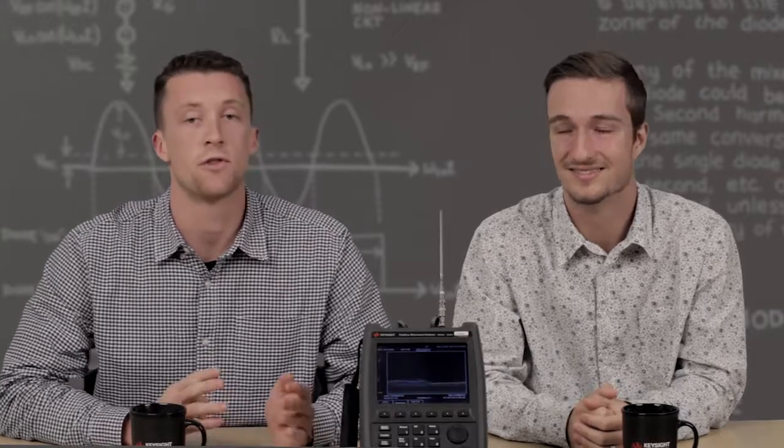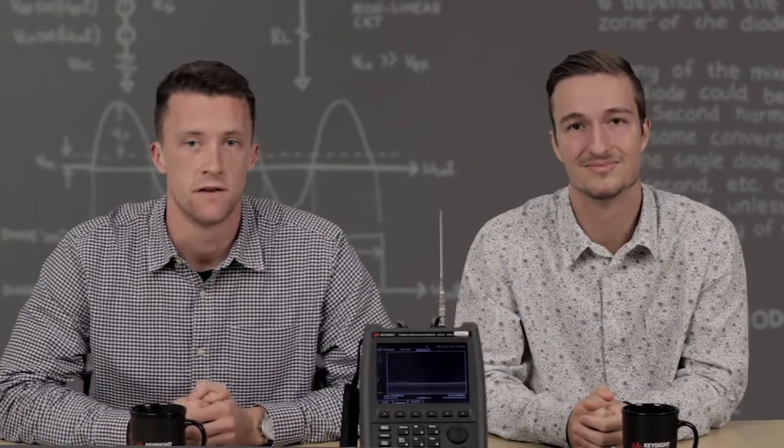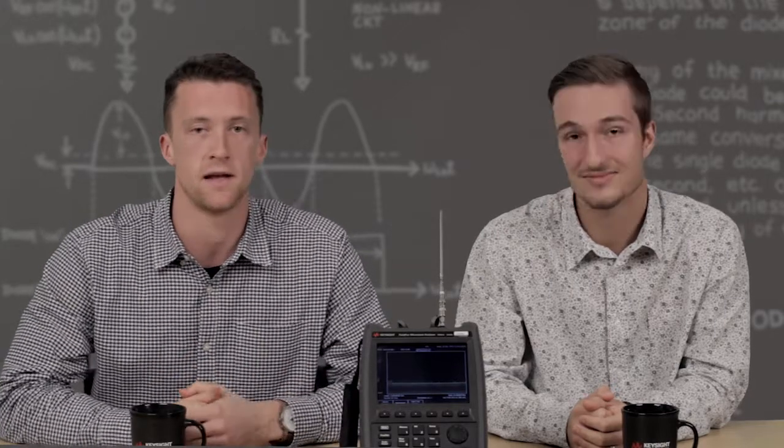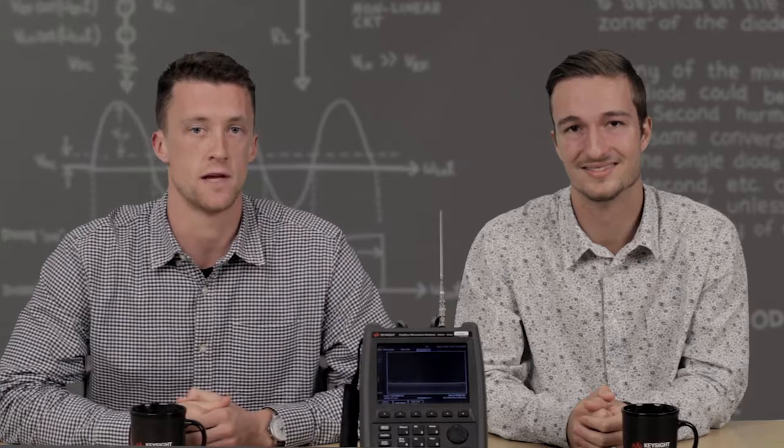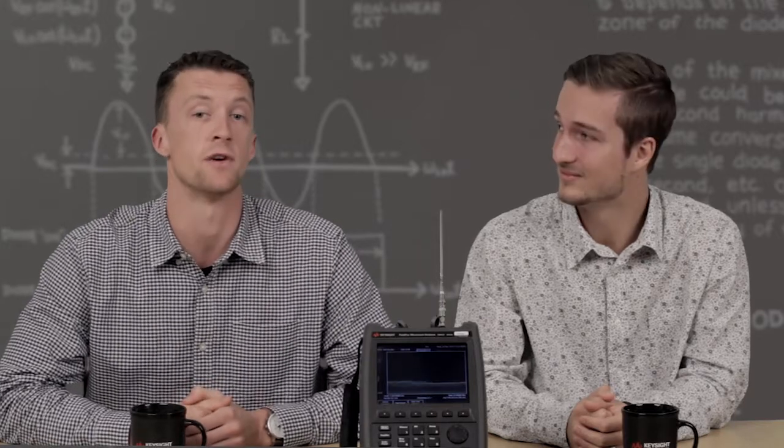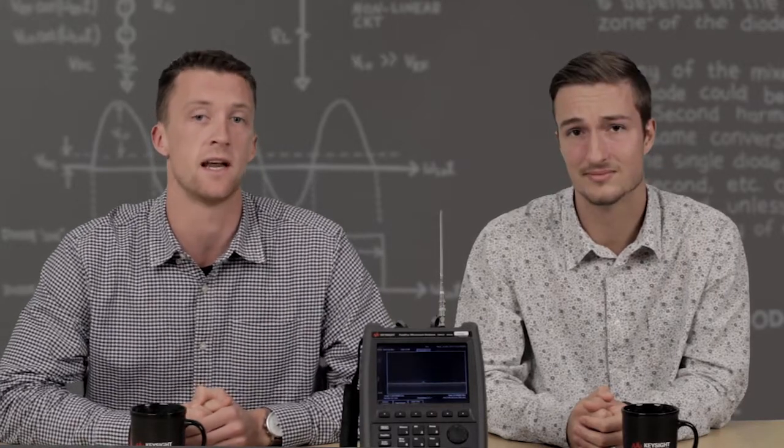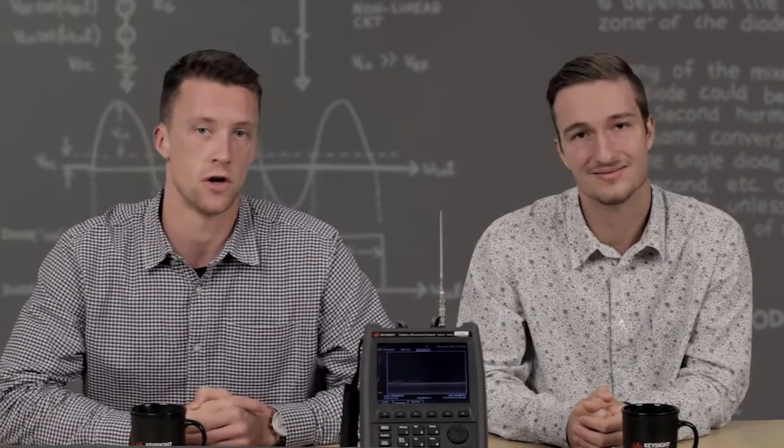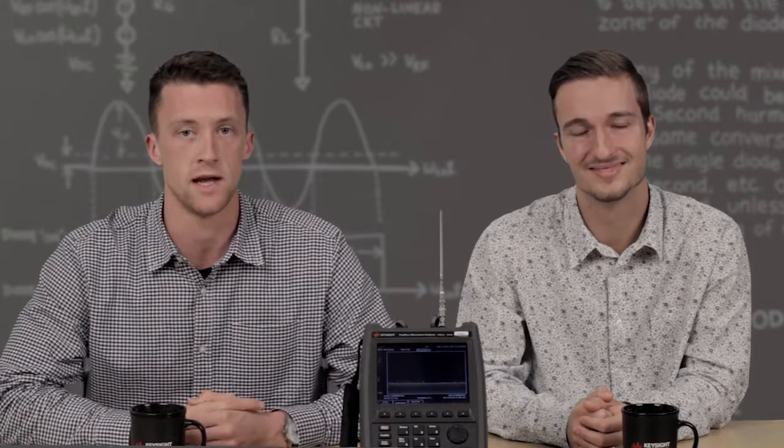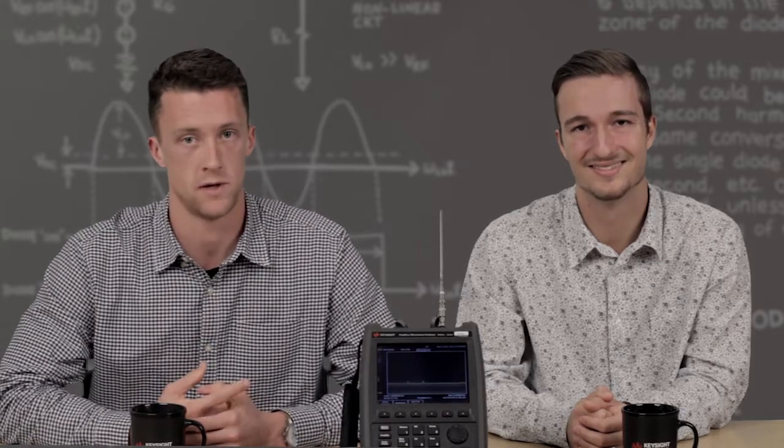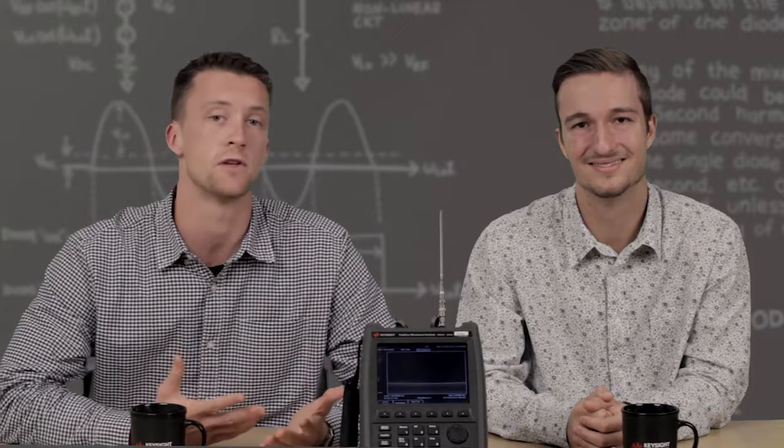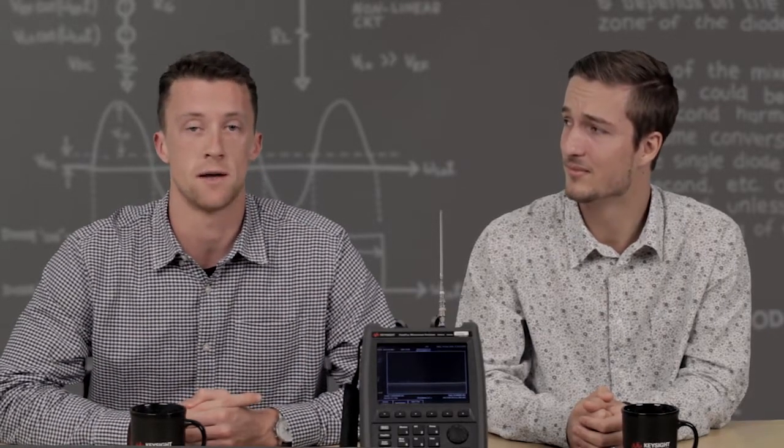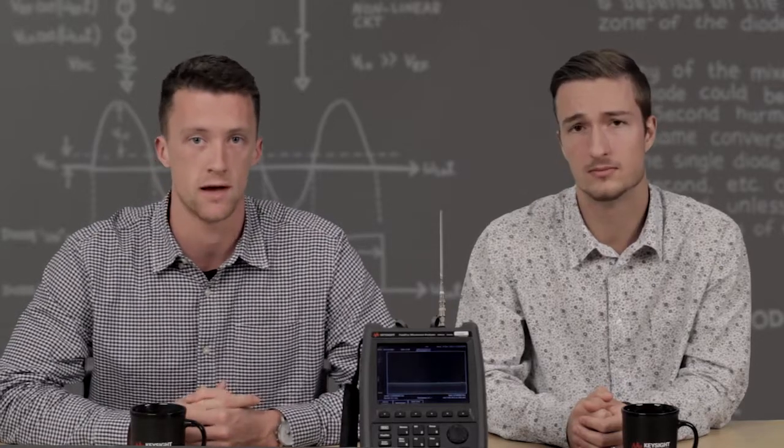And there are actually three modes of real-time operation on the FieldFox. The first one, real-time spectrum, essentially shows the same thing that the traditional SA mode does. It shows amplitude versus frequency. The only difference is that it is showing it instantaneously in real-time. The second mode, called density spectrum mode, shows amplitude versus frequency and frequency of occurrence, which makes this mode very useful for showing signals that fall on top of each other. The third mode, spectrogram mode, shows amplitude versus frequency and how these occur over time.